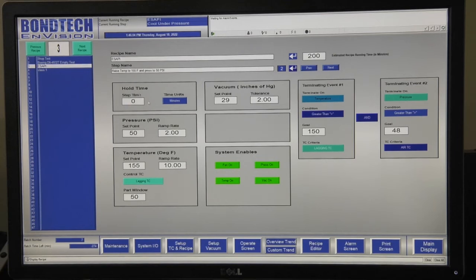Here's the recipe editor. This is how you'd actually set up the system for each particular recipe in the cycle, based on what that cycle requires. You go through and determine what your pressures, temperatures, and vacuum set points are going to be, how long you need to hold at that particular set point, and how quickly you need to reach that temperature or pressure. You can also control by leading, lagging, or the average of the thermocouples, and then enable which individual component needs to be enabled as far as the fan, pressure, temperature, vacuum, all the above, or none of the above.